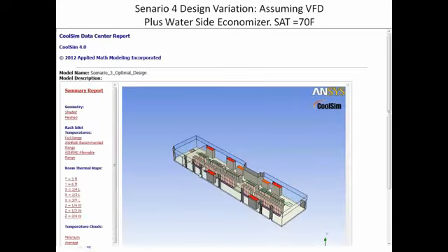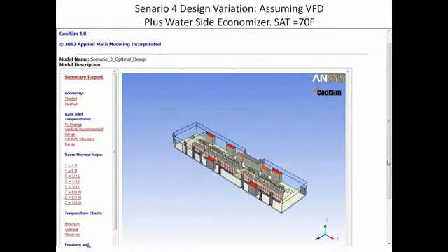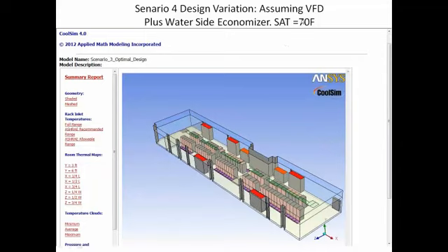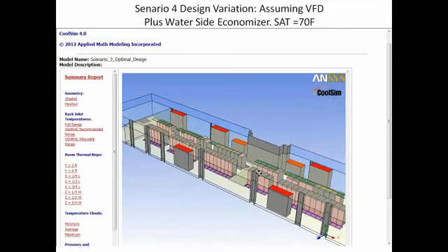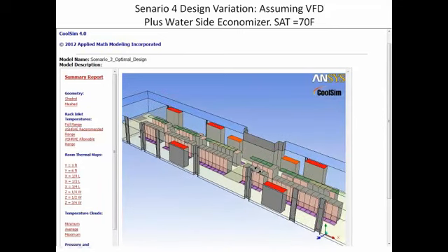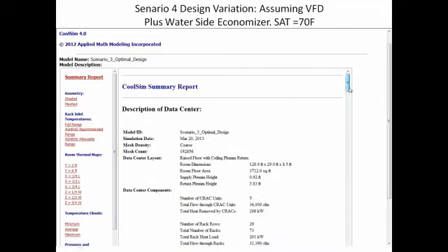Now in this case, I took it one step further for purposes of discussion today, Matt, and I said, all right, let's drive the supply air temp up to 70, and let's put VFDs in place, and let's drop them down 30%. So here I wiggled 2 parameters at once. I dropped the total flow rate for all CRACs down 30%, assuming we could put VFDs in place. And I assumed the water side economizer, which I believe is applicable in this case, right? Yes. And then I drove supply air temp up to 70 degrees F. Now, this one came out pretty well also. So let's take a look at what we've got.